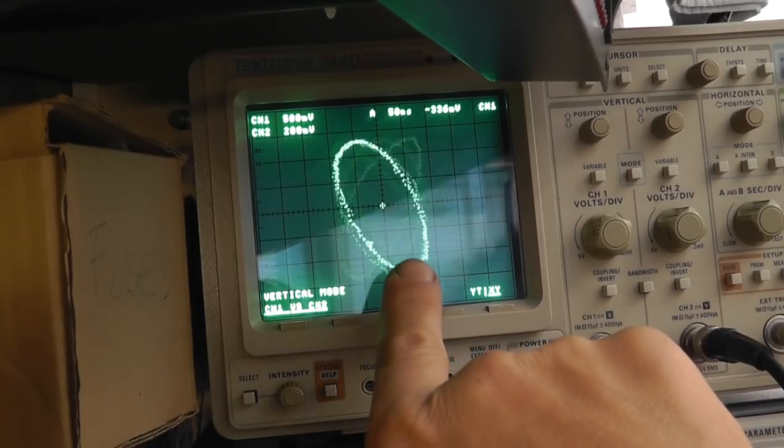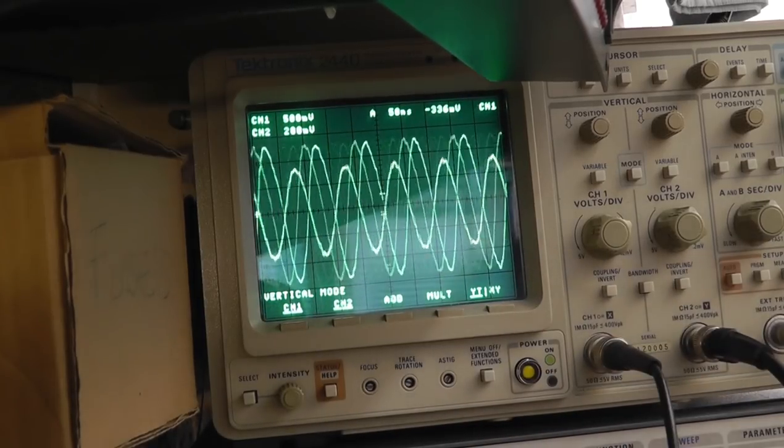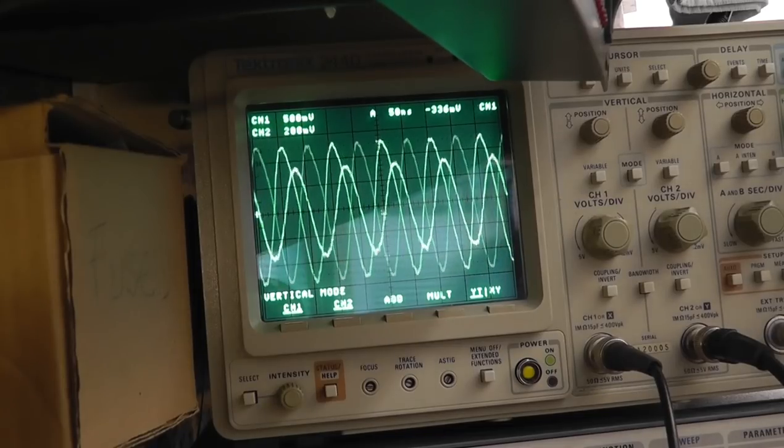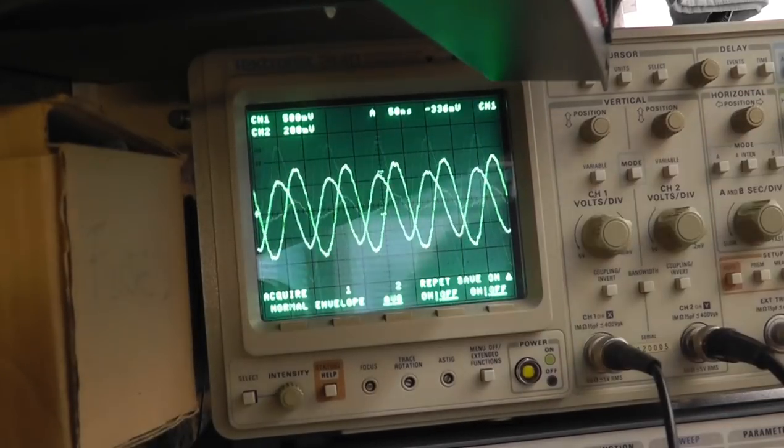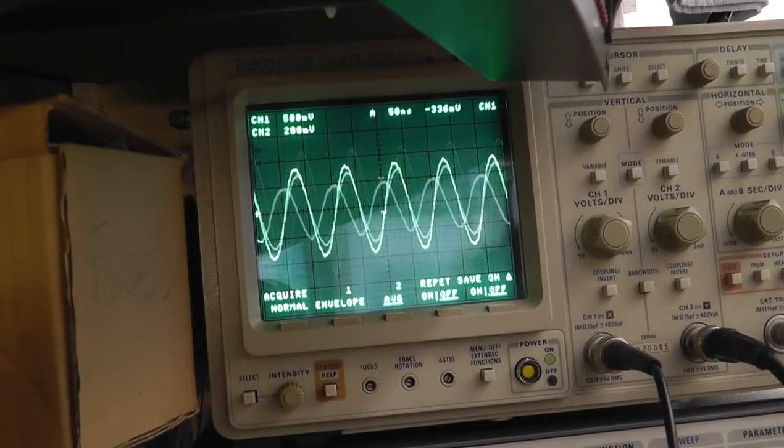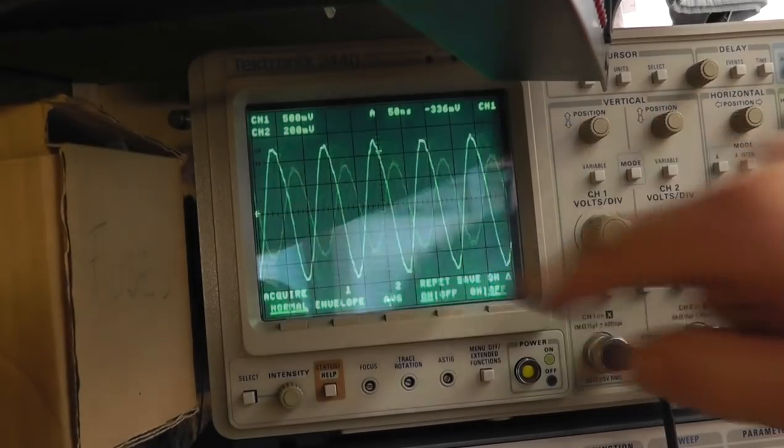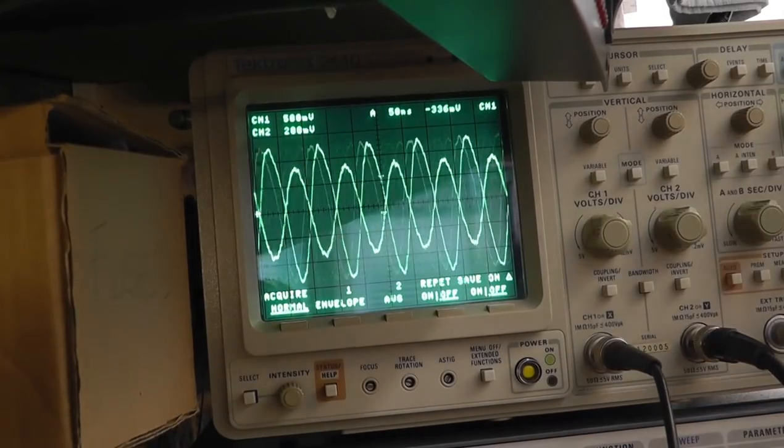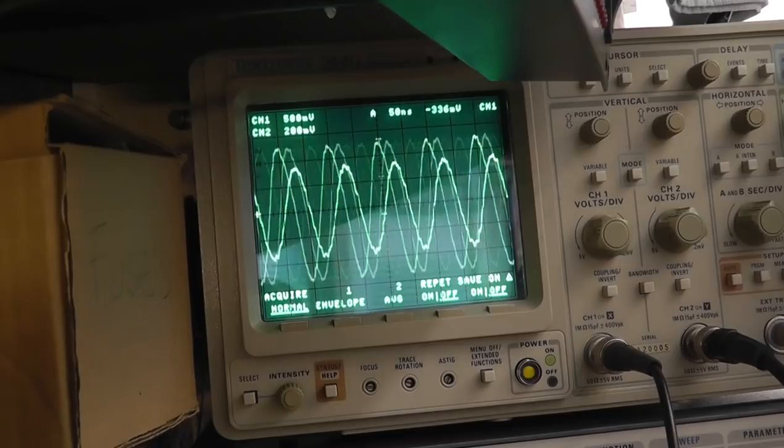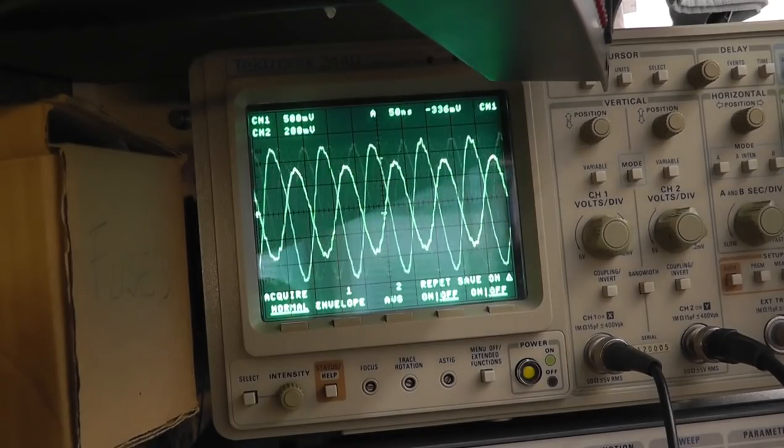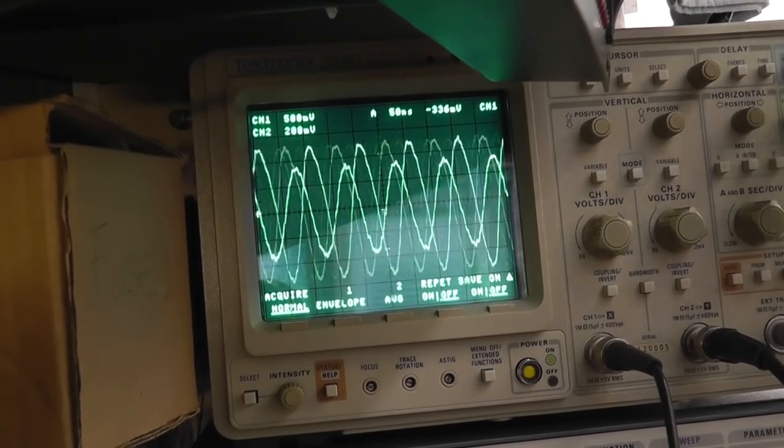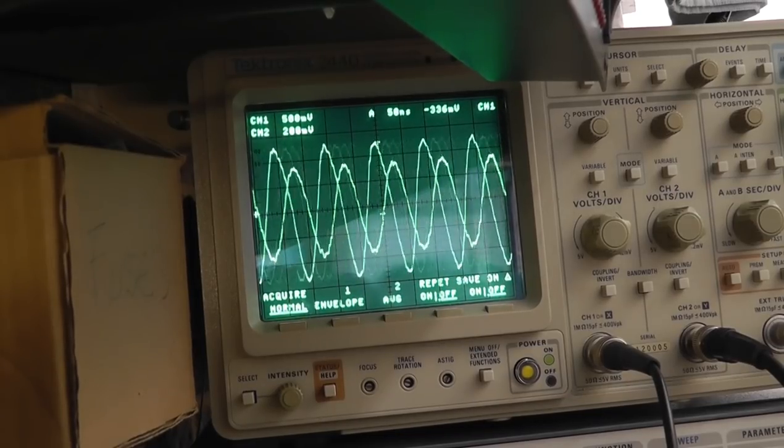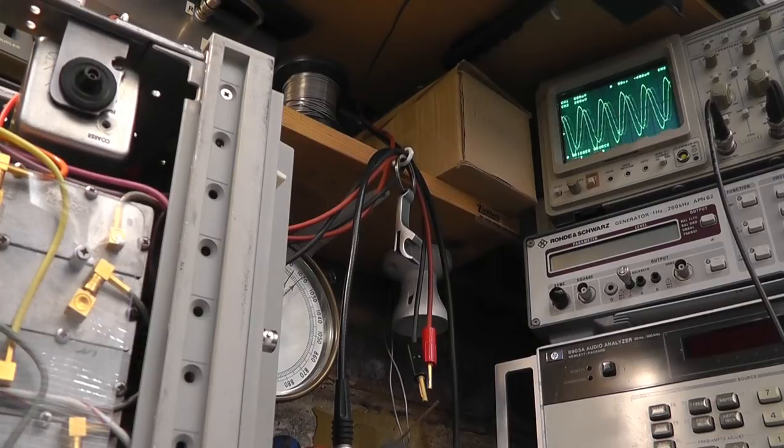You can see it's moving in and out of phase all the time. We need to let this oven oscillator warm up properly but it's a good sort of 10 hertz out of sync at the moment. Let's give this a little while and I'll come back and have a twiddle once it's nearer warm.